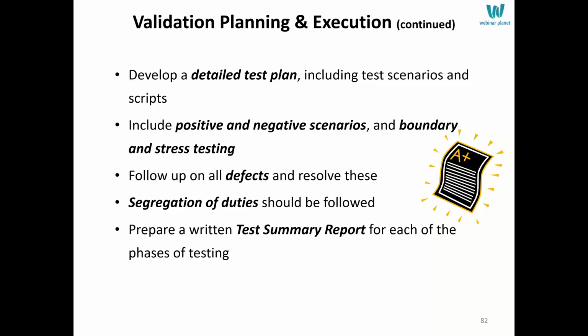Anytime you come across a defect, a deficiency, a deviation when you're testing, you have to investigate for root cause, you have to remediate, resolve it, and retest it. Segregation of duties has to be followed. No one should be able to review or approve their own work. And a summary report either at the end of each phase, IQ, OQ, PQ, or combining the phases in one summary report. But you have to be able to discern which phase you're talking about at any point in time.